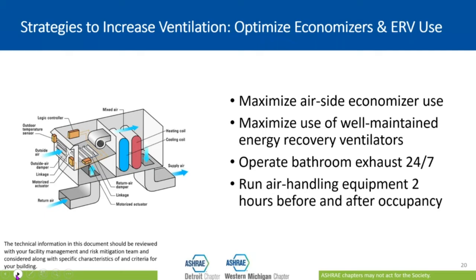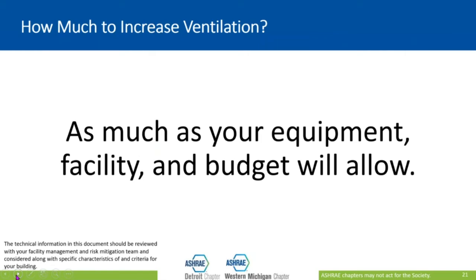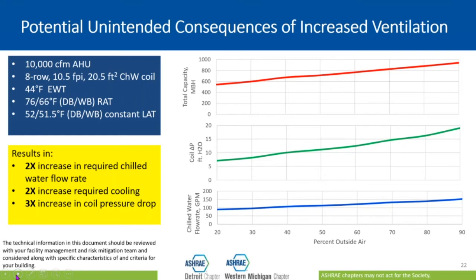And oftentimes people ask, how much ventilation should I be trying to bring in? And there's not a hard and fast number, right? Every facility is different, and so the answer is really as much as your facility and budget will allow. So we have to bear in mind that this increased ventilation does not come without a price. When we bring in additional air, it has to be cleaned. It's got to be heated, cooled, humidified, or dehumidified, and then delivered to the building. So that means that the HVAC equipment is going to be consuming more energy than it did previously.